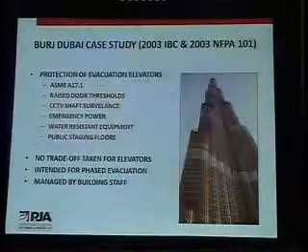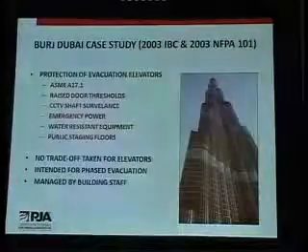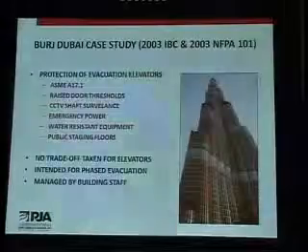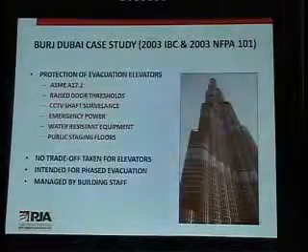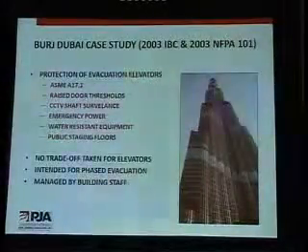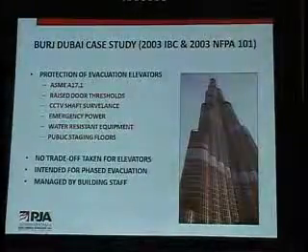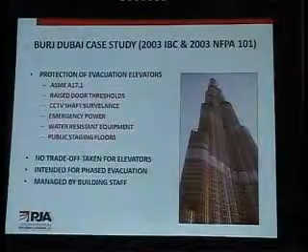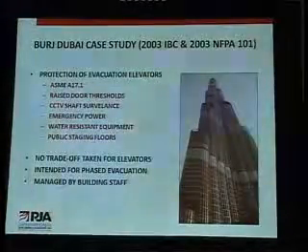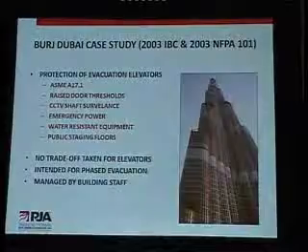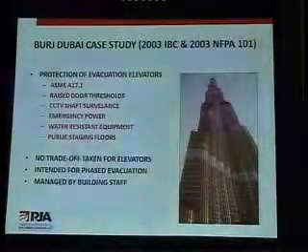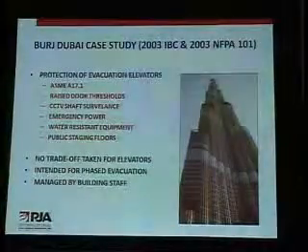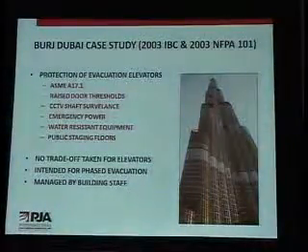But some things I want to highlight that Jim had left out was an additional protection of having CCTV surveillance cameras installed within each shaft on top of a lift, so that prior to the fire service or building staff undergoing a phased building evacuation, they can shuttle the elevator up and down the shaft to make sure that smoke hasn't entered the shaft, fire hasn't entered the shaft, and that the shaft hasn't been compromised, just adding an additional level of protection.